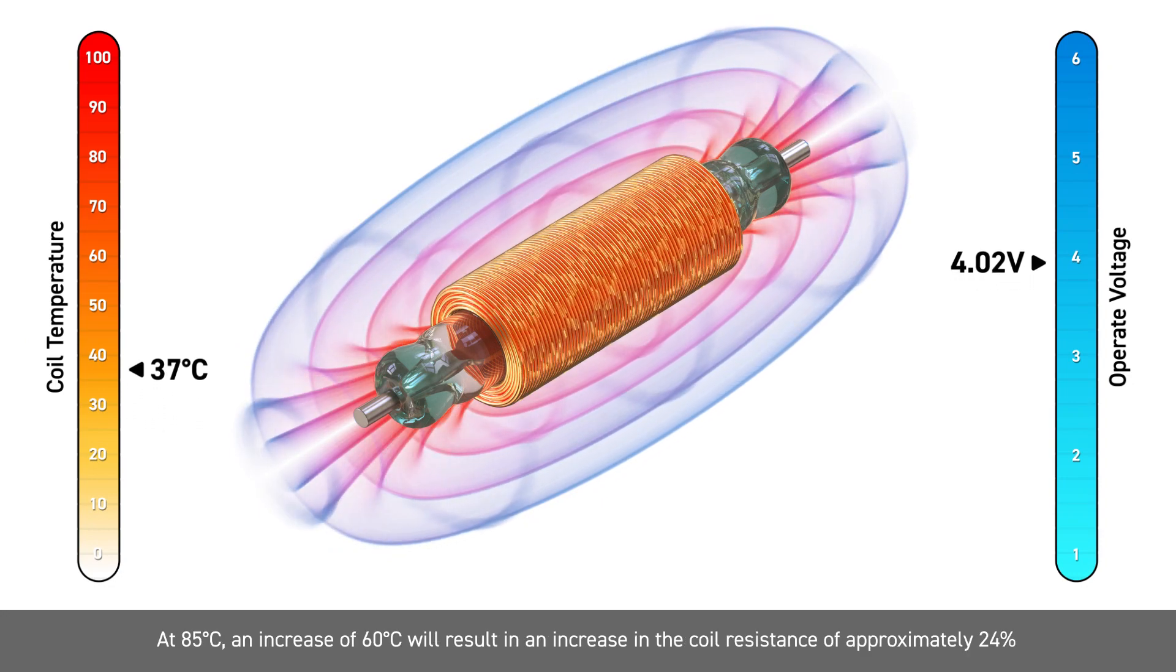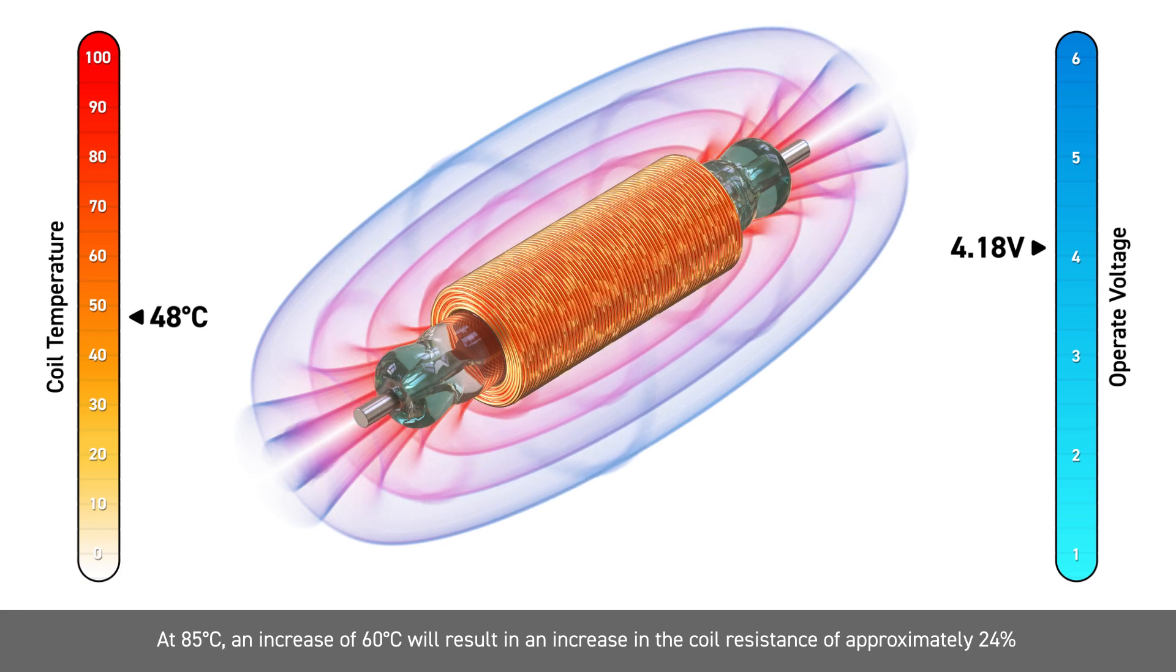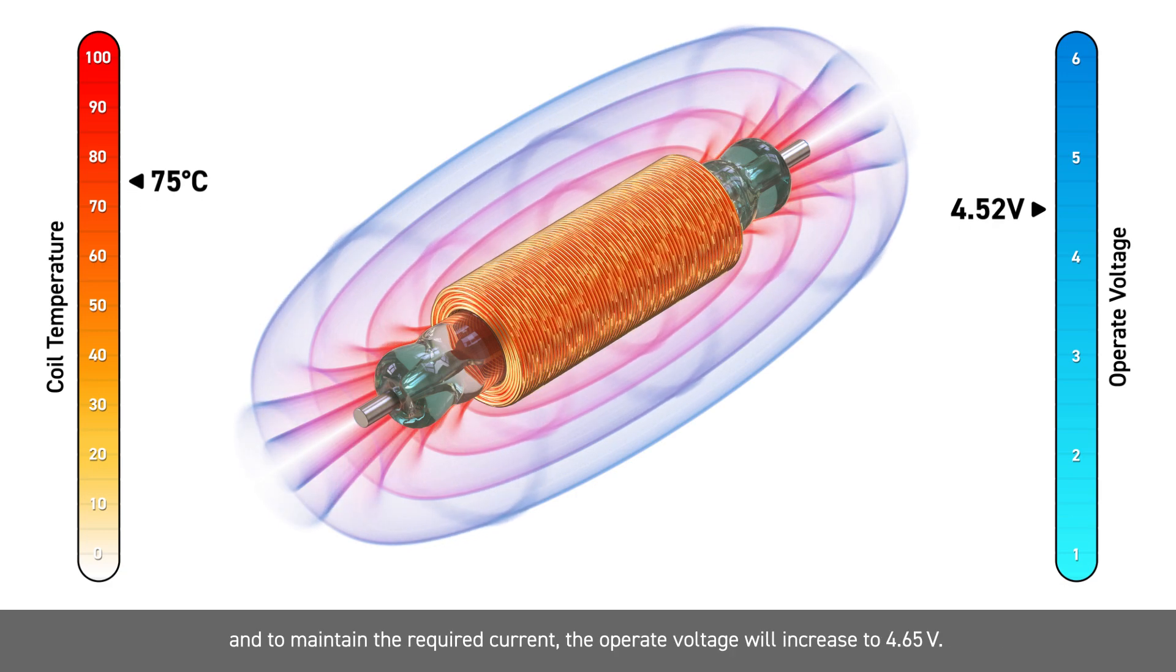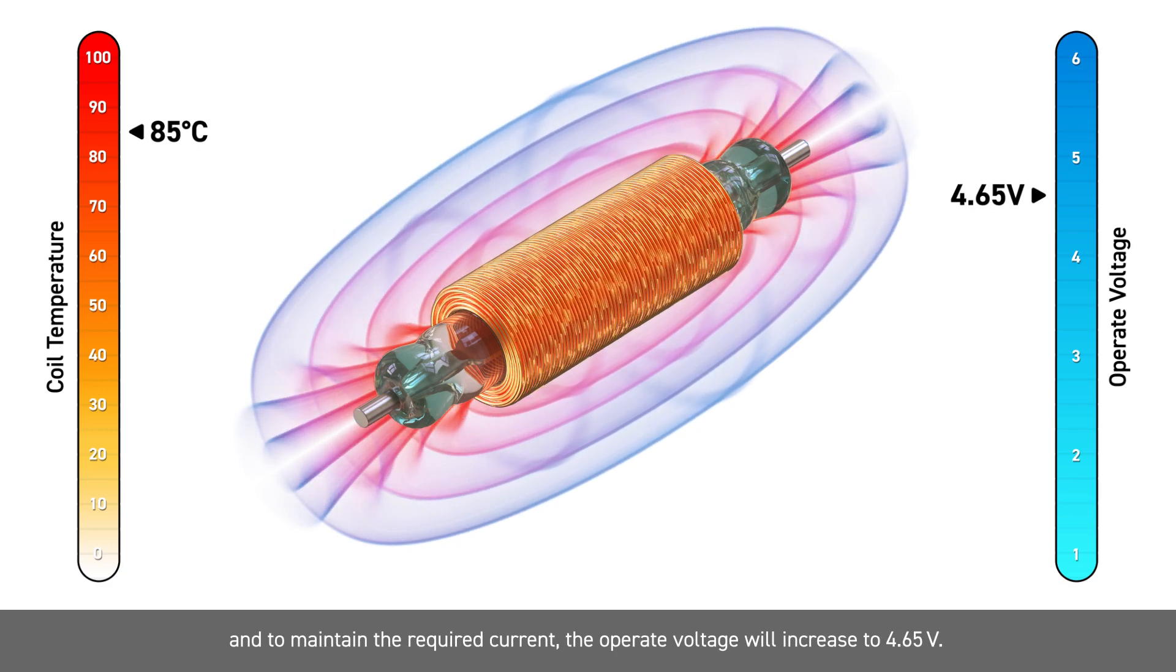At 85 degrees Celsius, an increase of 60 degrees will result in an increase in the coil resistance of approximately 24%, and to maintain the required current, the operate voltage will increase to 4.65 volts.